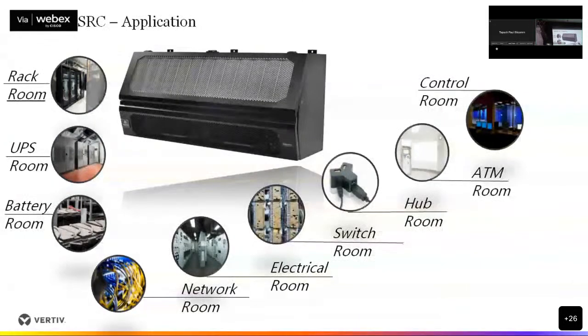Last and very important, in terms of capacity: comfort cooling machines are designed with 0.65 SHR (sensible heat ratio), whereas this is designed with 0.9 and above SHR. Typically for a UPS room, battery room, PLC room, utility room, switch room—any such room—your sensible load is very high. When you derive the capacity of a cooling machine, you have to derate it by 0.65 because it can handle only 65% of sensible heat; the rest is useless. Here you can design with 0.9 or 0.95, optimizing capacity, which reduces power consumption and improves performance.